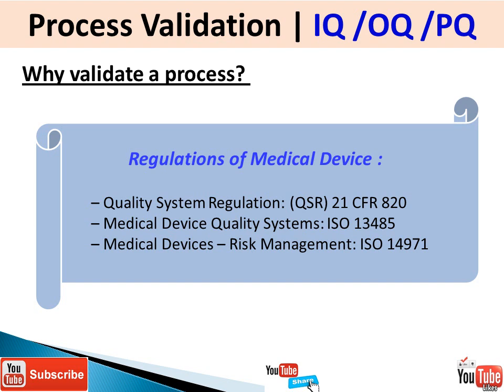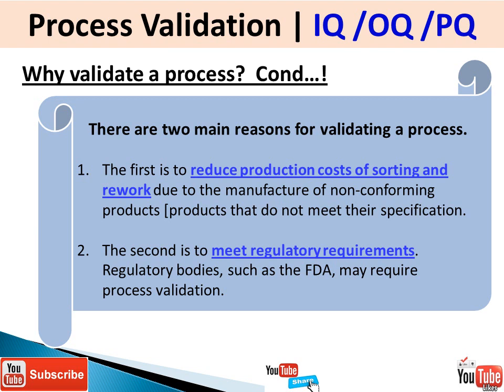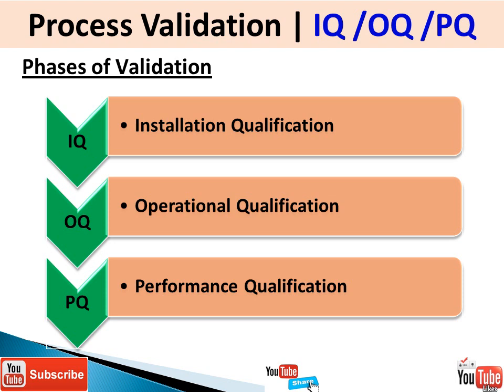So why do we need to validate a process? There are regulations and guidelines for medical devices requiring process validation, including 21 CFR Part 820 — the Quality System Regulation — and ISO 13485, as well as risk management standards. The two main reasons are: first, to reduce production costs associated with sorting and reworking, which ultimately saves money; and second, to meet the regulatory guidelines of bodies such as the FDA.